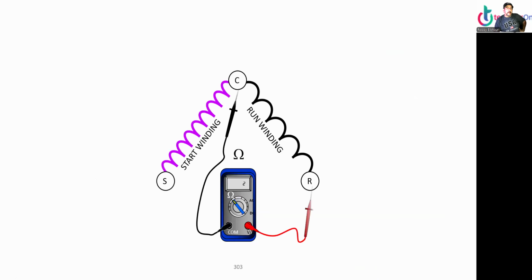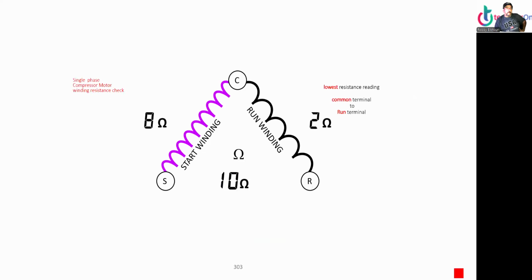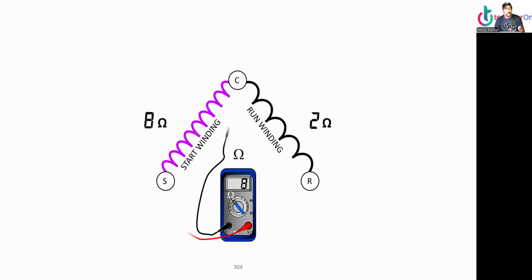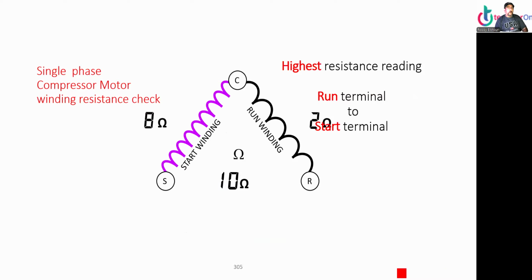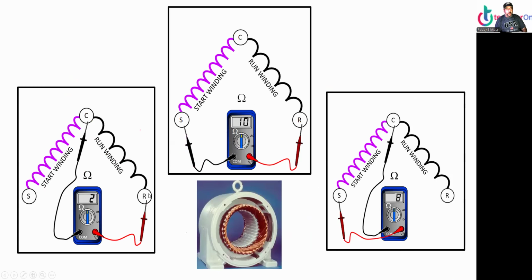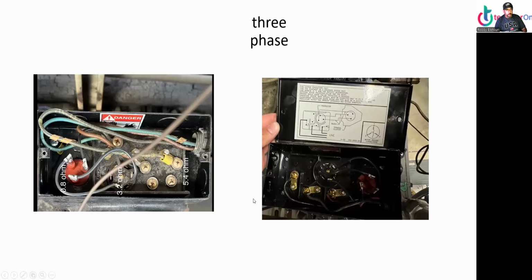Run windings, start windings. So the run winding should always be the smallest winding, 2 ohms. The start winding. Okay, this is not working here. How about there? Okay, here we go. So better this way. All right, so as you can see, between common and run, we have 2 ohms. And the one on the left, start and common, we have 8 ohms. Total is 10 ohms. That's how we know if it's working, if the resistance is proper on a single phase motor. Alrighty, so common and start plus common and run should equal start and run. Hope that makes sense. Now, three-phase compressors.